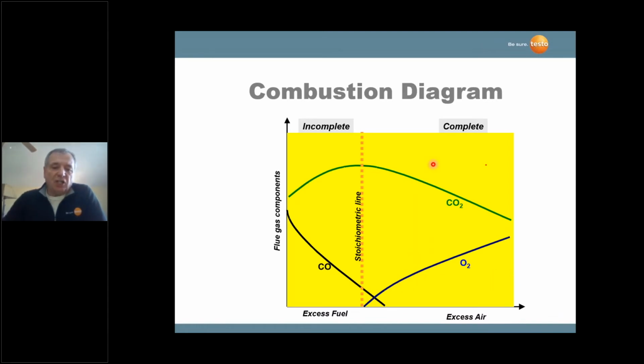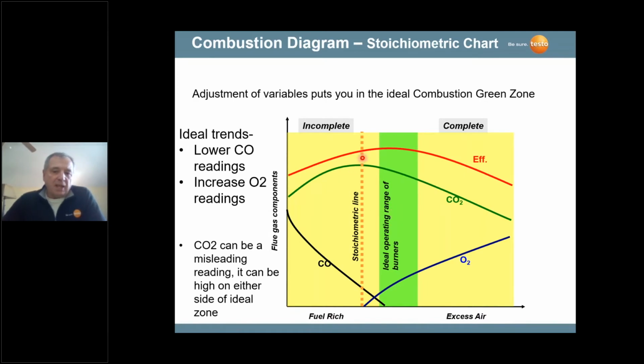So there's a section here where we want to operate our commercial boilers. And we want to operate these boilers, and I'm saying boilers, I'll talk a little bit about furnaces later, but boilers operate with between maybe 3% oxygen to 6% oxygen, high CO2, good combustion efficiency, and a trace of carbon monoxide. This is typically in gaseous fuels, okay? So on residential furnaces, we're usually farther away from the carbon monoxide line.